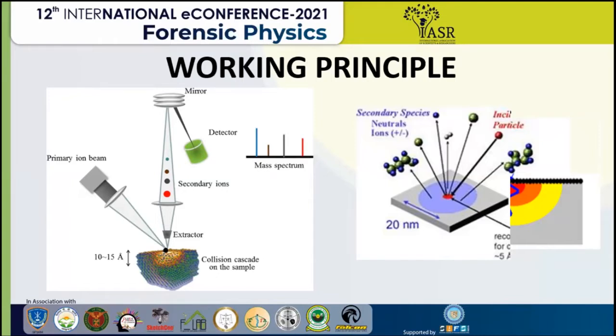The results of TOF-SIMS include a mass spectrum obtained by measuring arrival time at the detector after passing through the analyzer. It also produces a rastered beam that maps any mass of interest at a sub-micron scale, generating images of secondary ions from the rastered ion beam across the surface. It can also profile depth by etching the layers of the surface by sputtering under the ion beam.